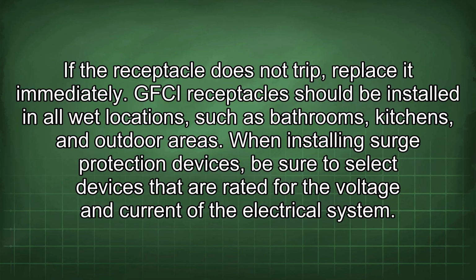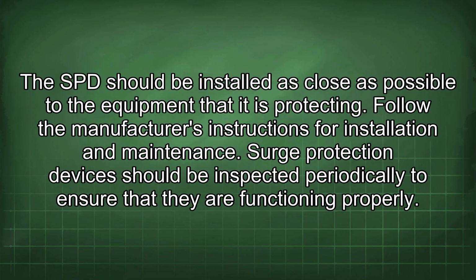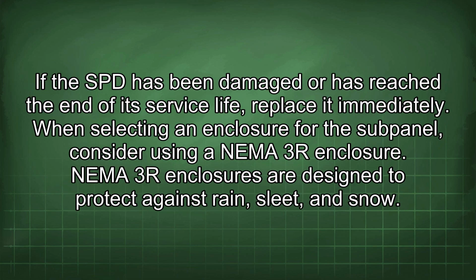When installing surge protection devices, be sure to select devices that are rated for the voltage and current of the electrical system. The SPD should be installed as close as possible to the equipment that it is protecting. Follow the manufacturer's instructions for installation and maintenance. Surge protection devices should be inspected periodically to ensure that they are functioning properly. If the SPD has been damaged or has reached the end of its service life, replace it immediately.